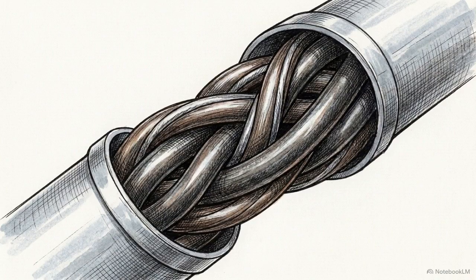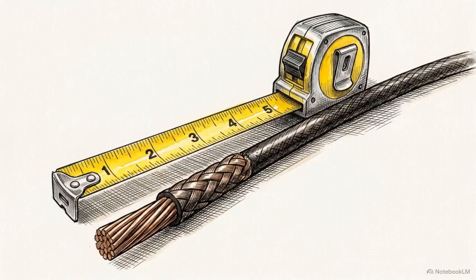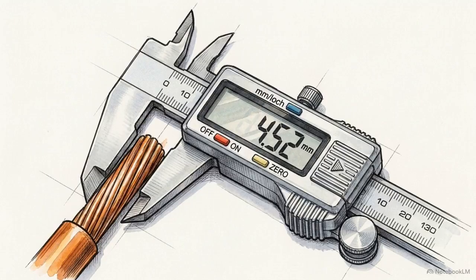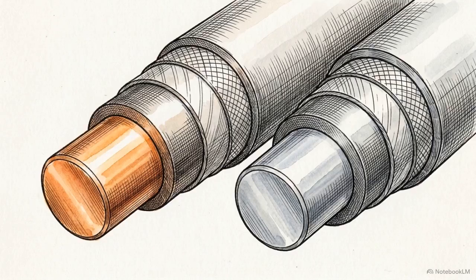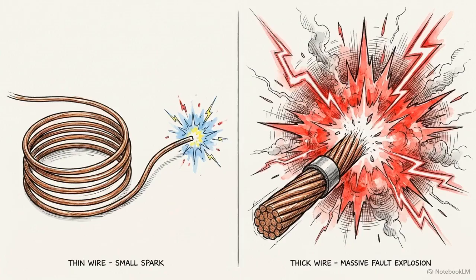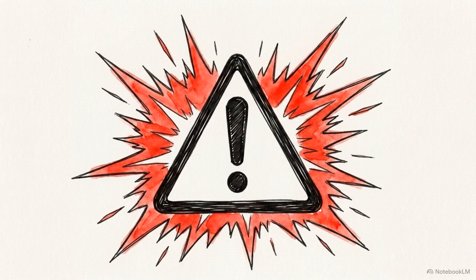Total phase impedance is highly variable. It depends on conductor length, the wire's cross-sectional thickness, and the choice of metal. This creates a counterintuitive engineering reality. Shortening a cable run or upgrading to a thicker, highly conductive wire actually increases the localized destructive capability of a short circuit.